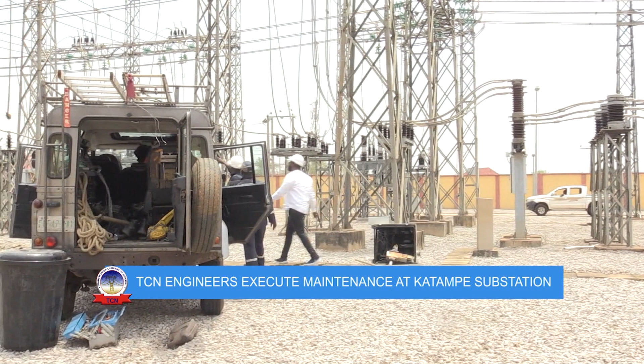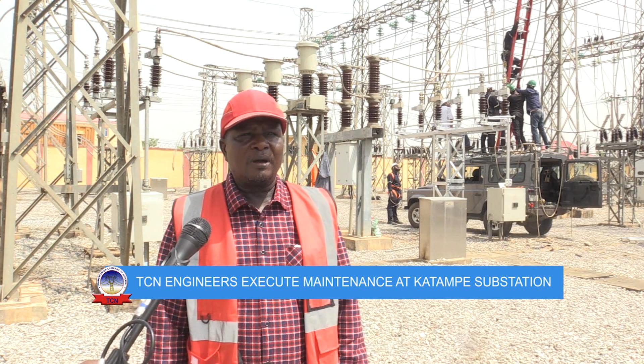Our Principal Manager, Transmission Abuja Sub-Region, Engineer Gabdo Chimda, further explained the process in the maintenance exercise: 'Here our linesmen are working on the down-dropper. We are preparing to evacuate load from this our new 100 MVA transformer, which very soon we are going to energize. That's why they had a problem on the line sometime back, on the down-dropper.